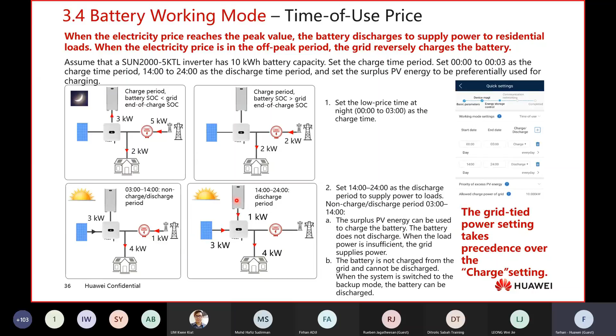So during that day, maybe your PV can generate only 3, and your load is 4. Then 1 will be taken from the grid, not from the Luna, because we do not allow the Luna to discharge power during this time. And the next period is from 2 PM until midnight. In this period the Luna is allowed to discharge. So you can see your load is 4 only. Your PV during this time is only 3 kilowatt, and then 1 will be taken from the battery. Let's say your PV is 0, then 4 will be taken from the battery until the battery power is depleted.